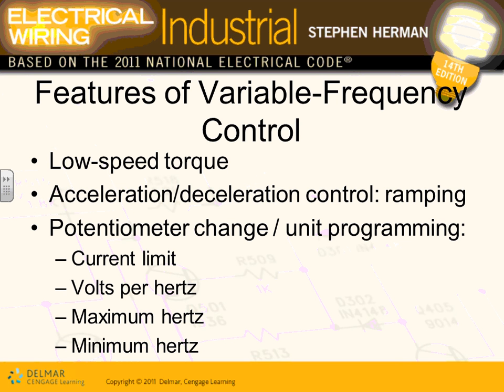One advantage, guys, also is you can take a single-phase system in your basement and feed a three-phase motor, though there is some derating happening here. If you're a farmer and you have a conveyor and you don't have a three-phase system, buy a VFD, tie it to the three-phase motor that you bought, tie it to your system, and derate it, typically to 80% of its rating. You can't run a 15 horsepower motor at 15 horsepower. You have to derate it a little bit. Basically, put less load on it, and you're good to go.